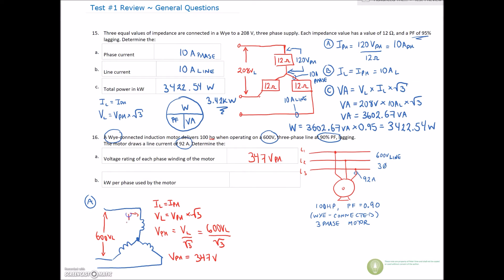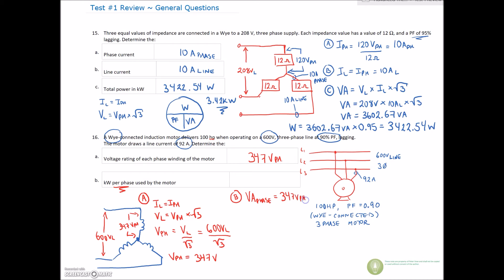So this voltage across each winding is 347 volts on the phase — any line-to-neutral voltage here is 347 volts. Now we need to find the kilowatts per phase used by the motor. We find the VA on the phase — that's our single-phase value. We have 347 volts on the phase. It's a Y-wound motor, so we have 92 amps on the line, which means 92 amps on the phase.